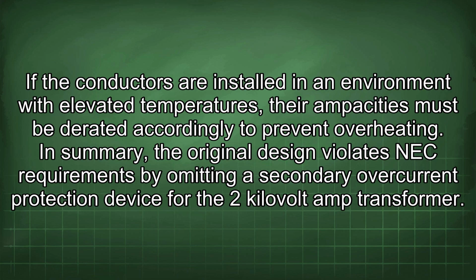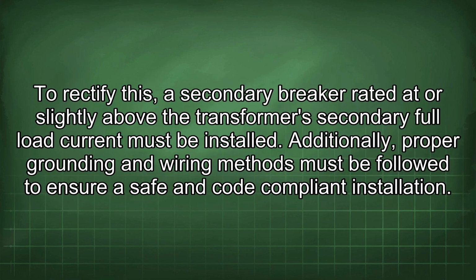In summary, the original design violates NEC requirements by omitting a secondary overcurrent protection device for the 2 kVA transformer. To rectify this, a secondary breaker rated at or slightly above the transformer's secondary full load current must be installed. Additionally, proper grounding and wiring methods must be followed to ensure a safe and code-compliant installation.